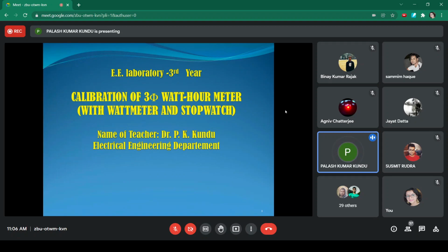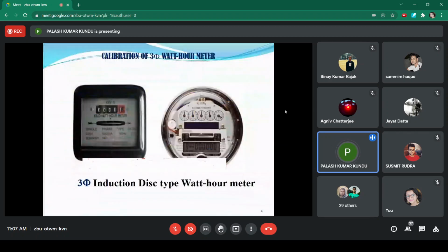There is a two-element watt-hour meter for a three-phase system, so that the driving torque is proportional to the sum of the power consumed over a definite interval of time, and that is called the three-phase energy consumed in a three-phase circuit or three-phase system. So this is a typical look of a commercial type three-phase energy meter, which consists of a disc. The rotation of the disc is a measure of the energy being consumed when the meter is connected to the three-phase circuit.